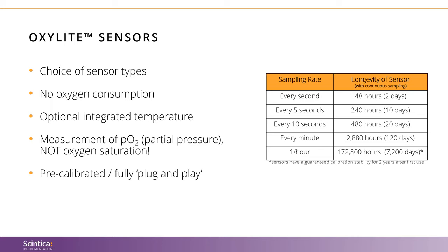Let's take a look at some of the OxyLite sensors. Oxford Optronix offers a wide range of oxygen sensors to meet requirements of various experimental models. Each sensor does not alter oxygen content in the tissue when measuring, and each sensor has the option of integrating temperature sensing for auto-compensation of the PO2 measurement. All sensors come pre-calibrated, and that calibration is guaranteed for two years — truly a plug-and-play system. Longevity of the sensor depends on the operating sampling rate. The oxygen sensors are consumable as the dye eventually gets photobleached with use. The user can easily select from a list of sampling rate presets through the touchscreen interface on the Pro and ProXL models, with examples of sampling rates and corresponding sensor longevity shown in the table on the right-hand side of the screen.